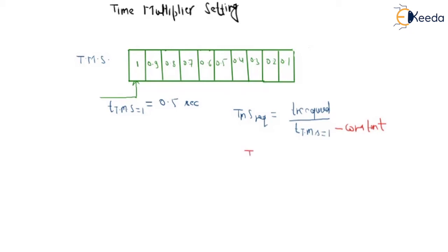So TMS2 upon TMS1 is equal to T2 upon T1. It means this is how we will change the value of TMS and we can get the corresponding changes in time. Let us assume corresponding to TMS equal to 1, the operating time is 0.5 seconds.